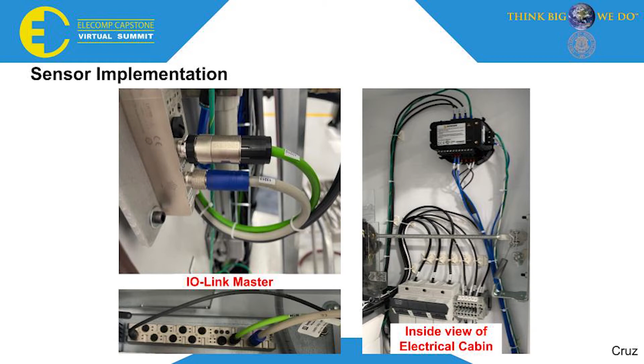We worked on configuring mainly the power meter, since we realized the power reading wasn't accurate enough as it was stock. We found that we needed to add more current transformers to adjust the scaling and make it more accurate, then connected that to the PLC.